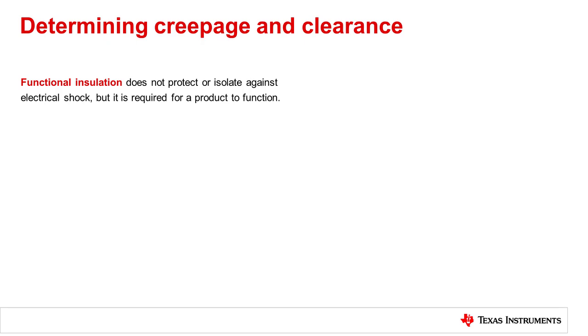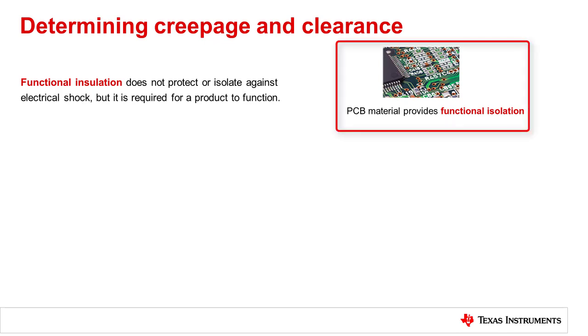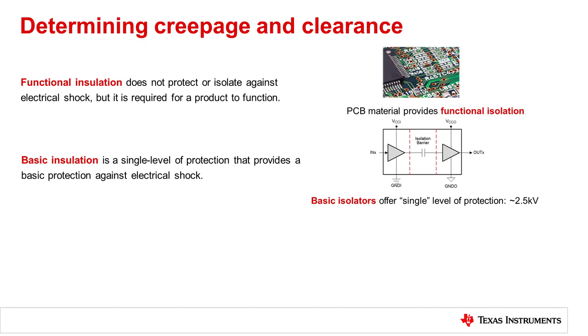Functional insulation does not protect or isolate against electrical shock, but it is required for a product to function. A good example may be the PCB material between metal traces on a board — the circuit would not function without separation of the traces, so this functional insulation is needed to operate. Basic insulation is a single level of protection that provides basic protection against electrical shock. A very common example would be the plastic insulation of an electrical cord, which is a single level of protection from AC voltages.